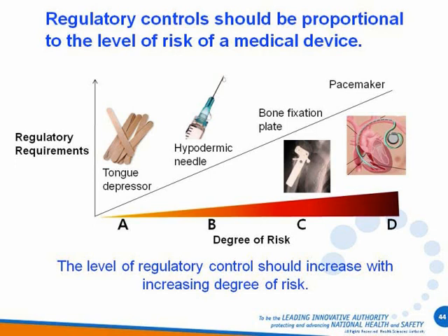The risk presented by a particular medical device depends on a number of factors: its intended purpose, its intended user, its mode of operation, and the effectiveness of the risk management techniques applied during design, manufacture, and use.